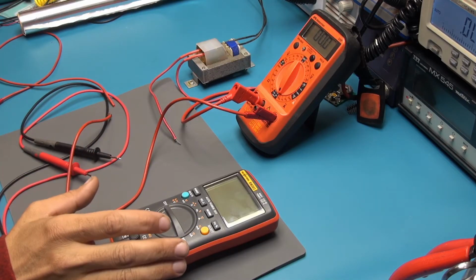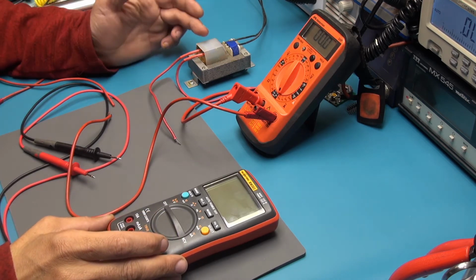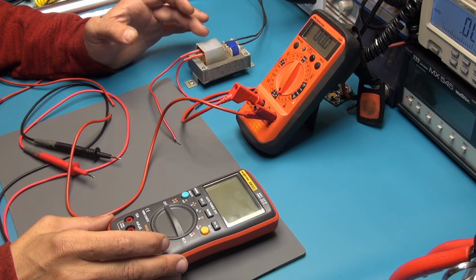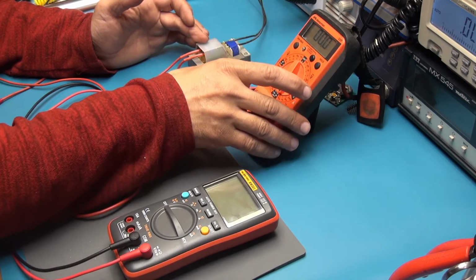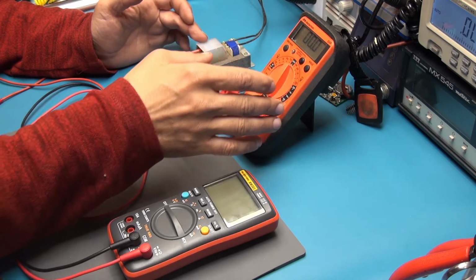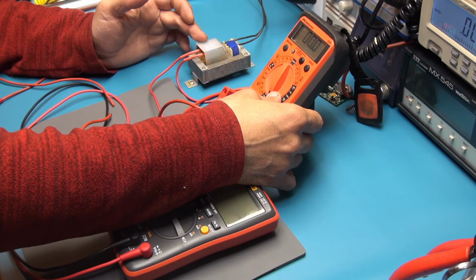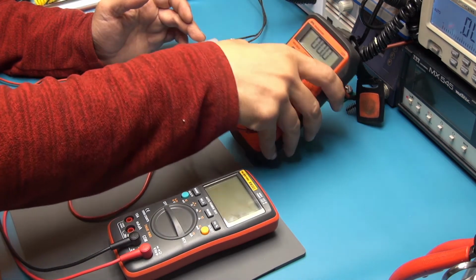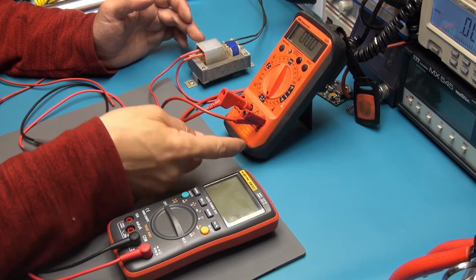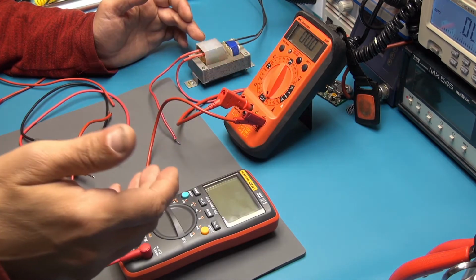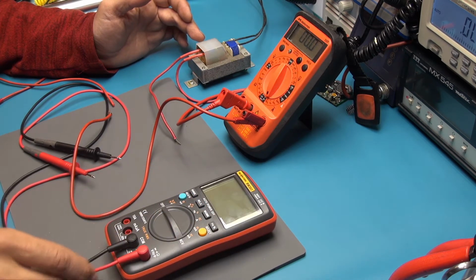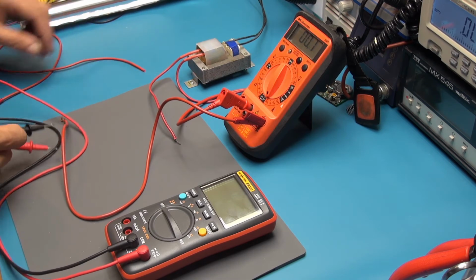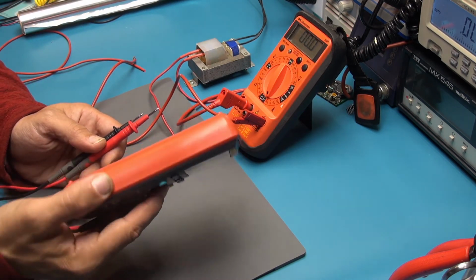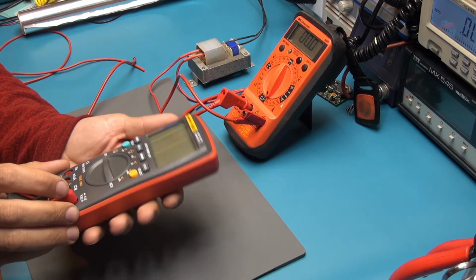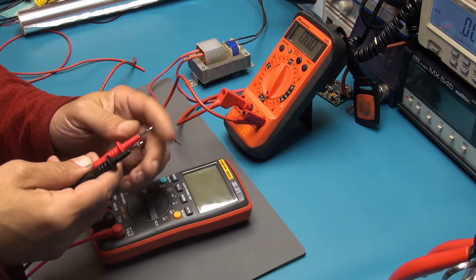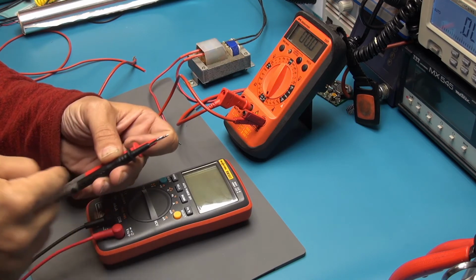Okay, here for the high voltage insulation test, we are going to use a high voltage generator, which works in alternating voltage, and we are going to read the current going through with this microamp alternating current meter, which is a simple multimeter but with a 200 microamp caliber, and it is able to read some current going through the plastic and other wires actually. So what we are going to do here is to test the insulation of the plastic of this device according to the voltage which can go through the connectors and through the plastic.